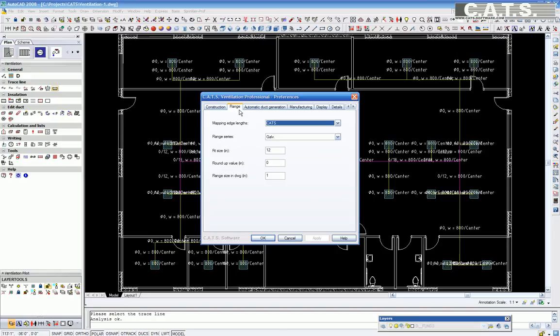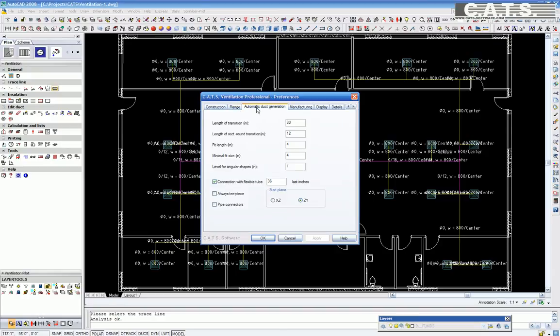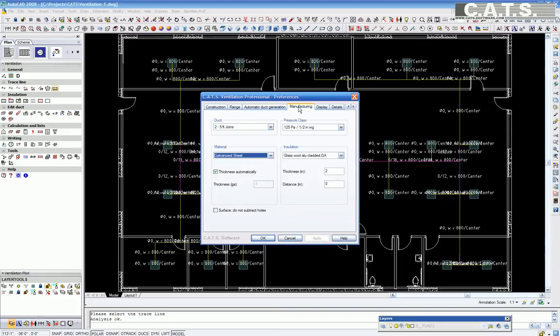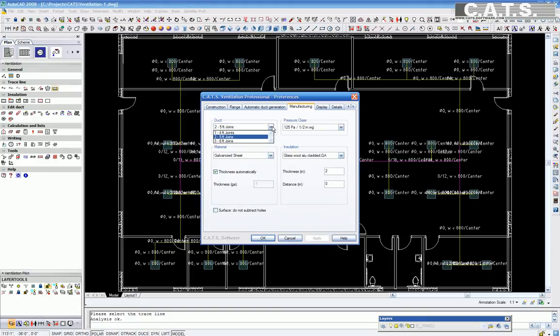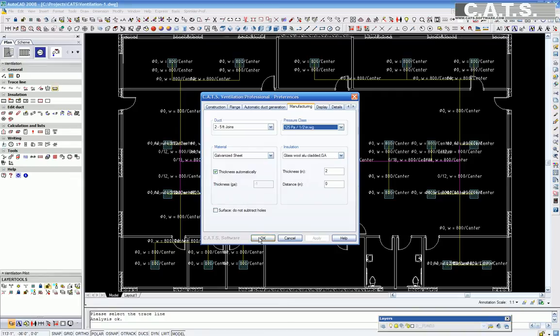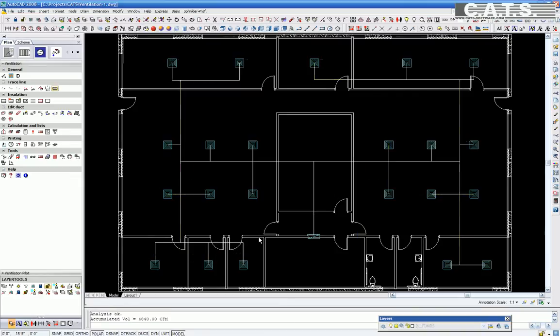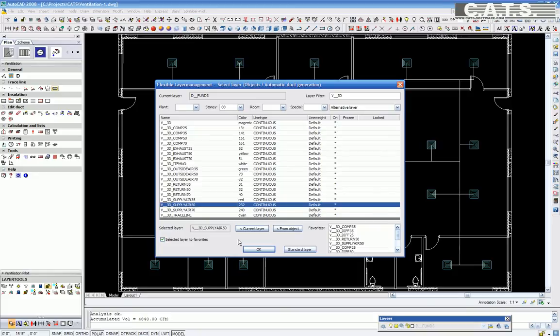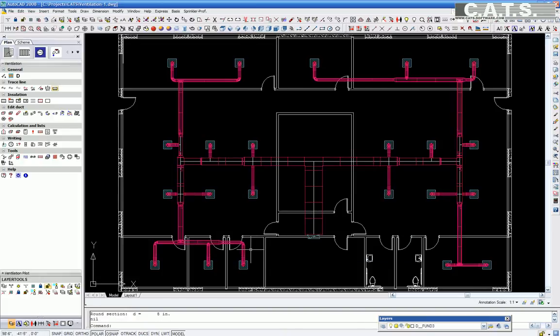Under the range, we have our settings on default. Under automatic duct generation, we have the length of transition set at a maximum of 30 inches. The length of rectangular to round transition is 12 inches. And a maximum connection of flexible tube of 36 inches. The next tab is Manufacturing. All specifications are set to SMACNA Standards. Select OK. A window appears with a flexible layer management. We will select the layer for Supply Duct. The software will now create the three-dimensional drawing.